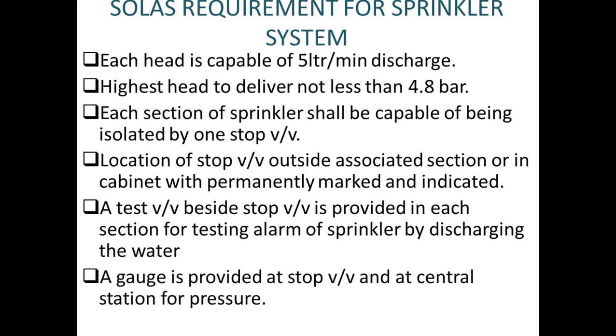Now, each section of sprinkler shall be capable of being isolated by one stop valve. Each section of sprinkler shall be capable of being isolated by one stop valve. The stop valve shall be located outside the associated section or in a cabinet, and permanently marked and indicated. This stop valve is basically a means of isolation. It has to be located outside the section it serves. For example, for X section, the stop valve must be located outside X section or in the cabinet, with a permanent marking indicating that this is the stop valve.